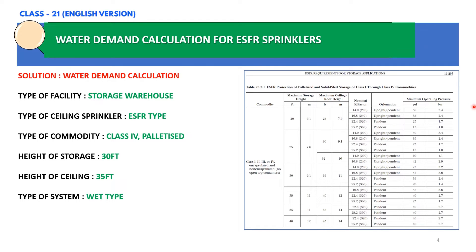If you want to select ESFR sprinklers for other types of commodity, you need to select the appropriate table. You can refer to Chapter 23 of NFPA 13, 2019 edition. This table covers ESFR sprinklers for Class 1 through Class 4 commodities for palletized and solid piled storage areas.